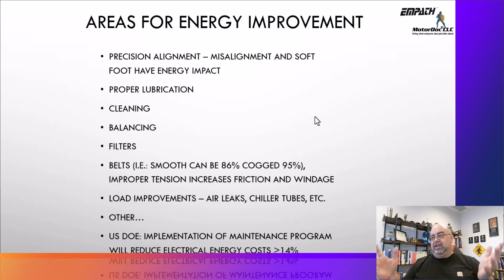That was a study done in the 1990s. Precision alignment, misalignment, and soft foot have a huge energy impact. Proper lubrication has an impact. Cleaning the motor has an impact. Balancing the motor has an impact. Not huge, but it's there. All these losses, when we're measuring the kilowatt or watt value, add up across 6,000 or 8,000 hours a year. Those losses go into heat, sound, and vibration, which is important for the next part.